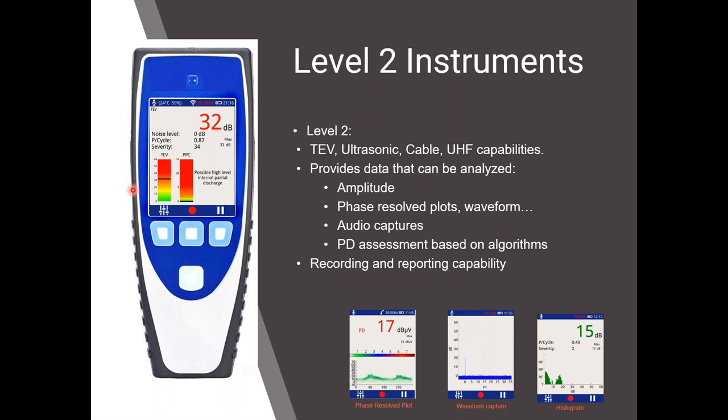It gives you amplitudes, your pulse per cycle count, your phase resolved plots, your waveform captures. It gives us all the data we need to accurately determine not only the presence of PD, but how bad it is. What is its severity? Typically, it's going to allow you to do multiple tests: your TEV, your ultrasonic, cable, UHF. It gives you your amplitudes, so it's got recording capabilities.